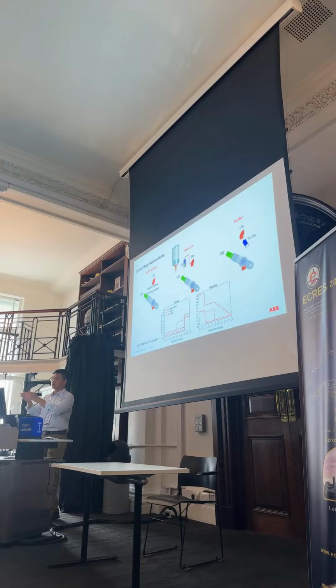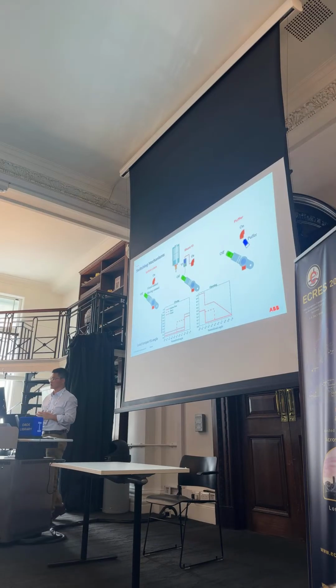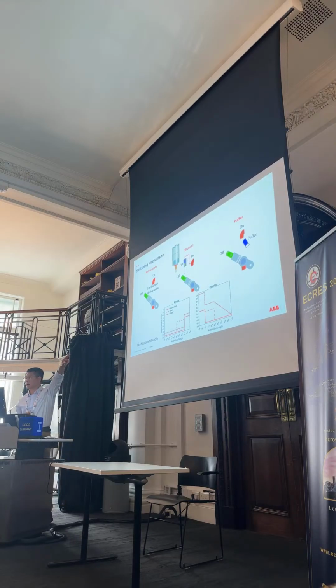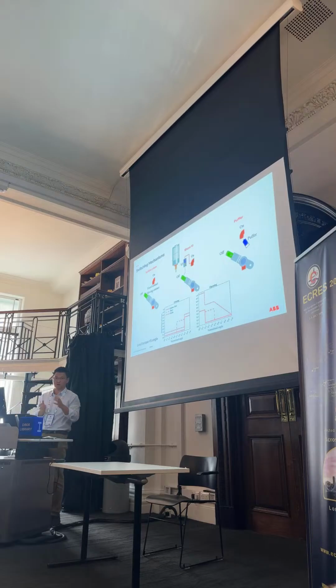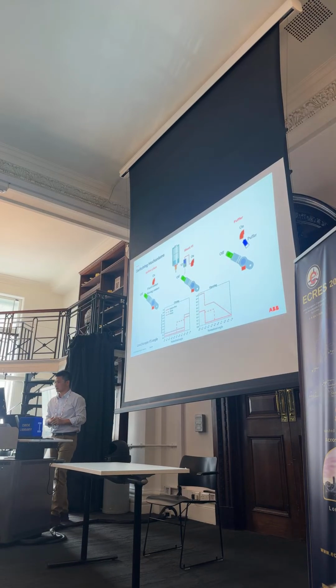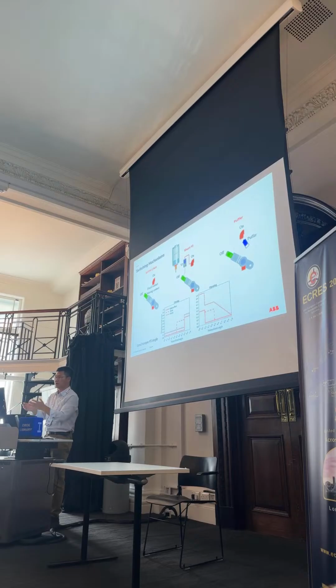Of course, I cannot show you all of the details due to confidentiality here, but that is the best function. Normally these vacuum interrupters are used in circuit breakers, not in load break switches, but here we use this high vacuum also for switching load break switches. Of course, the cost will increase.